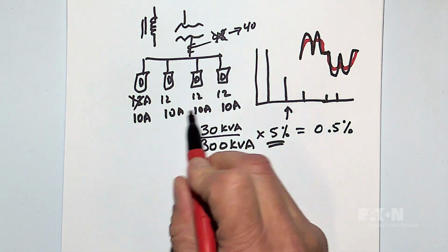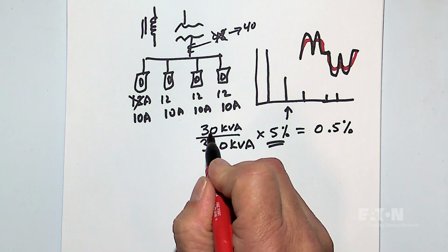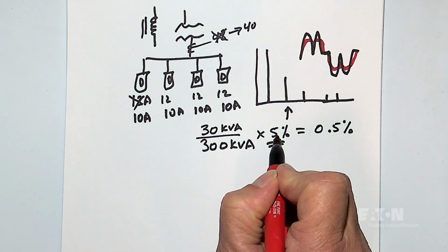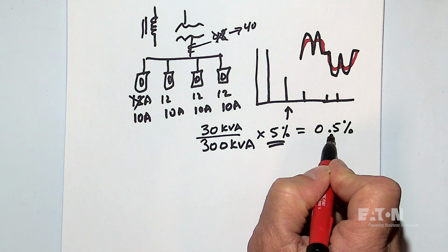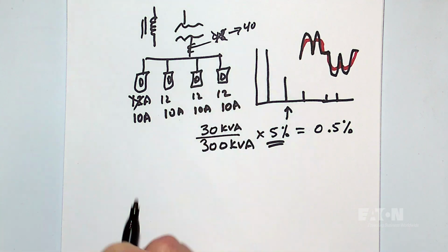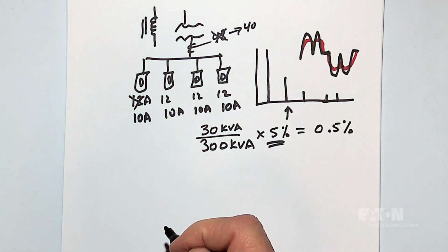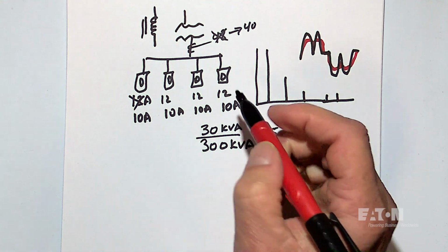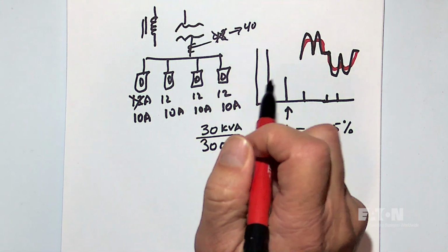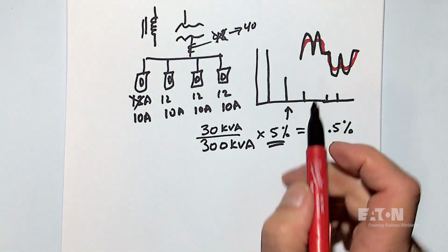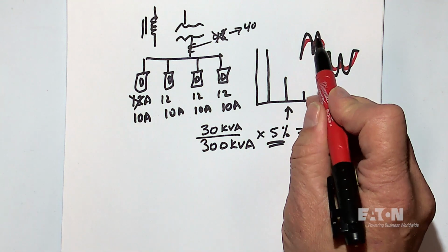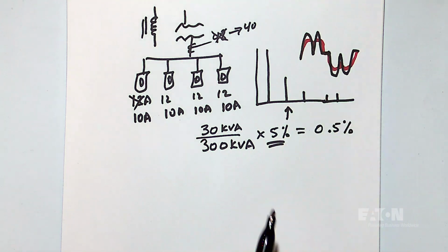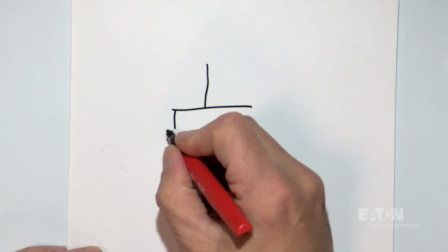But as you see, as you add more and more drives to here, this number becomes bigger. And as a percentage of the total impedance, this number becomes bigger. So then this looks more and more like a line reactor. And so really that's the case. And so as the current flows up through the transformer, this constricts the flow, and we reduce the harmonic current from something that looks steep to something that looks a little more smoothed out, like we've talked about many times with line reactors.